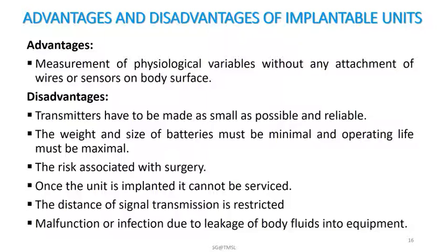Third is the risk which is associated with surgery. Fourth, once the unit is implanted, it cannot be serviced, and the life of that unit depends on how long the battery can supply the necessary current.